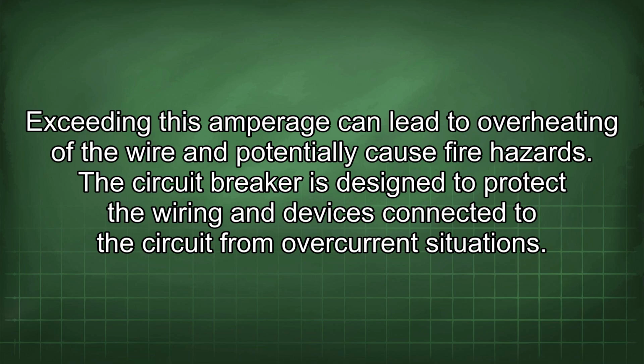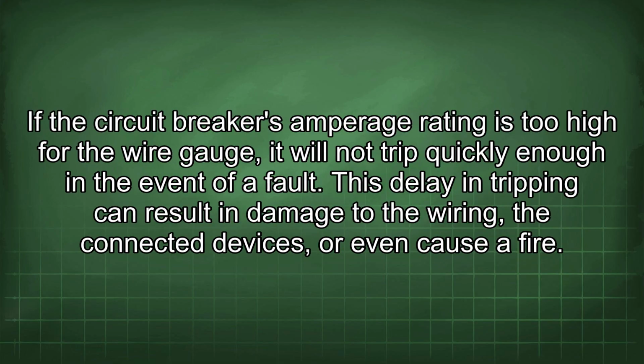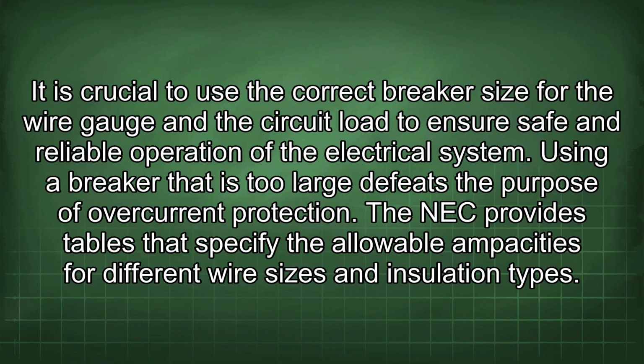The circuit breaker is designed to protect the wiring and devices connected to the circuit from overcurrent situations. If the circuit breaker's amperage rating is too high for the wire gauge, it will not trip quickly enough in the event of a fault. This delay in tripping can result in damage to the wiring, the connected devices, or even cause a fire. It is crucial to use the correct breaker size for the wire gauge and the circuit load to ensure safe and reliable operation of the electrical system.